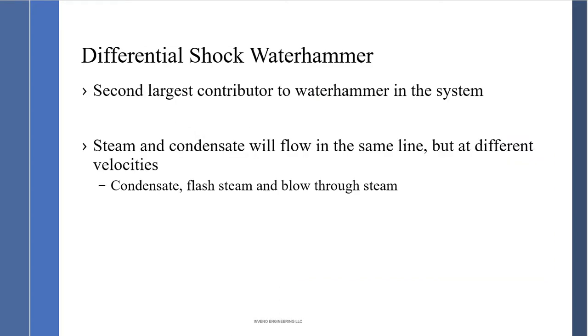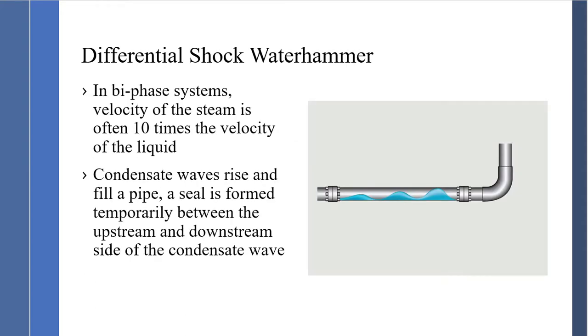Differential shock water hammer is the second largest contributor to water hammer in the system. Steam and condensate flow in the same condensate line at different velocities. The condensate line carries condensate, flash steam, and blow-through steam from failed steam traps and bypass valves. When velocities exceed 4,500 feet per minute in the condensate lines, a wave is created. When that wave seals at the top and bottom and hits an elbow, it causes a violent reaction called differential shock water hammer.